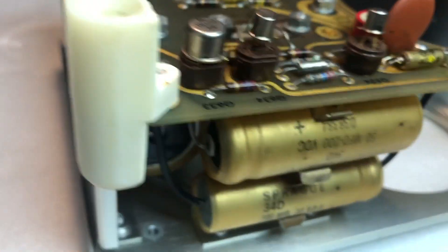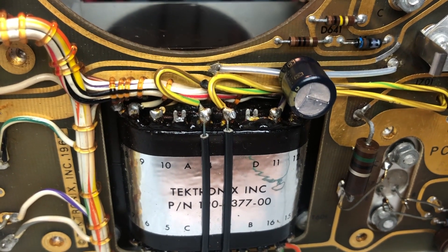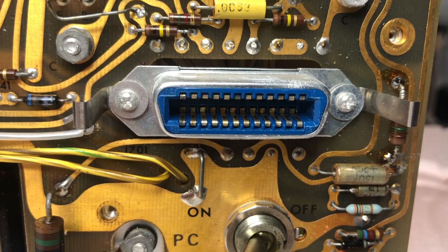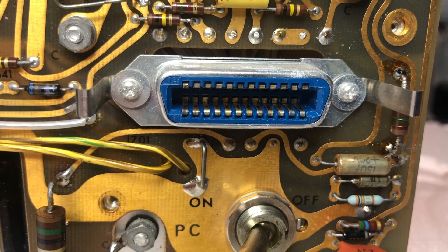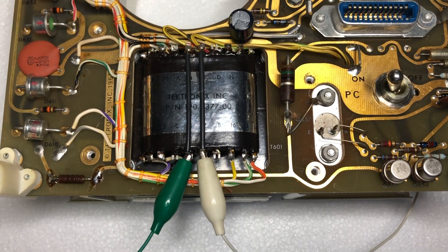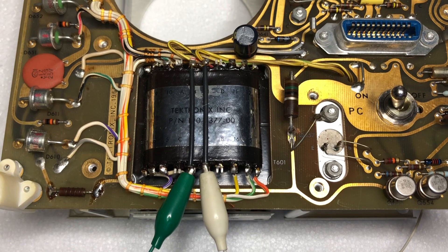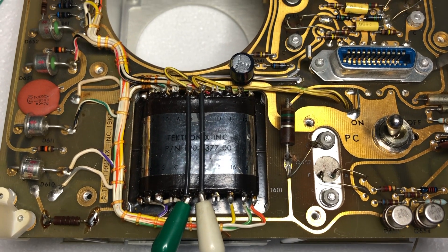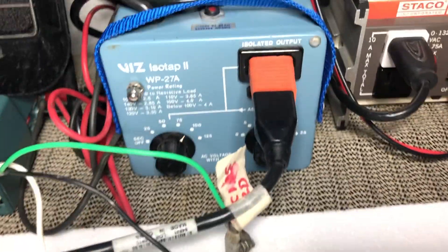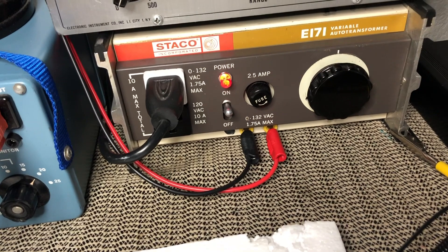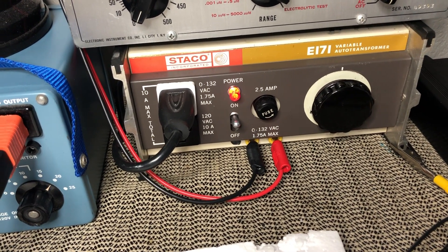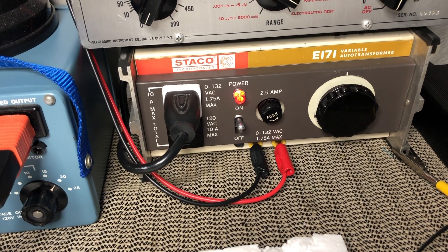These two are the incoming power to the transformer. I'm going to bypass the whole AC interlock and power switch and then measure the output on the connector directly. I just want to see if all the rails are present or not. This is pin number one and this is pin number 24. That's how I'm going to apply direct AC voltage to the power supply unit, bypassing the AC interlock and the indicator unit. Let me warn you: if you are not familiar with electronics or newbie electronics, please do not follow because this is dangerous. The connection comes directly here to the isolation transformer, and the isolation transformer is connected to the variac. I'm going to be increasing the voltage maybe to half of what is expected to start with, then I'll go full line voltage and measure the outputs.